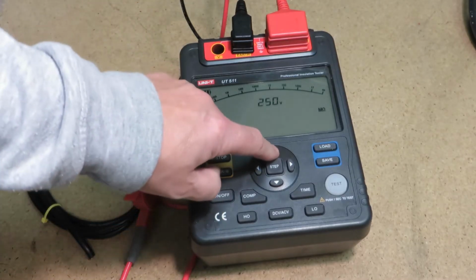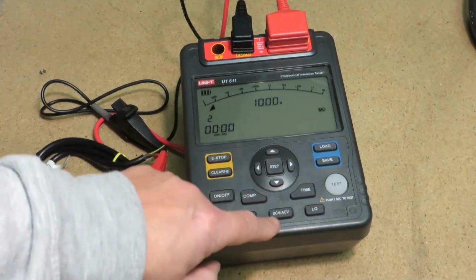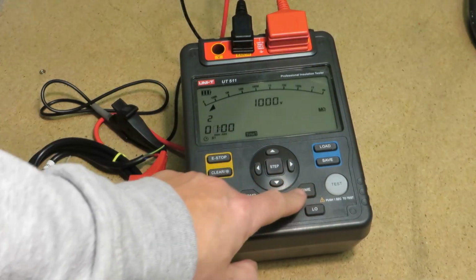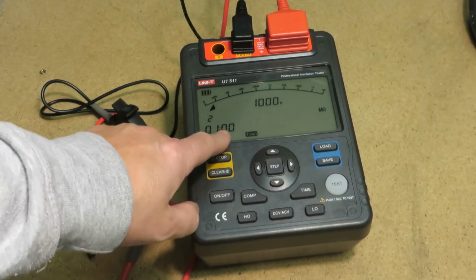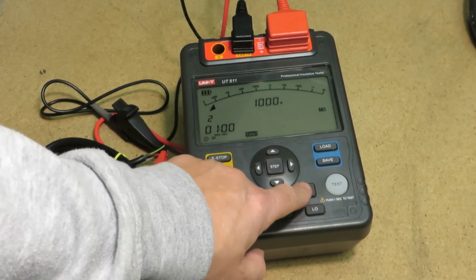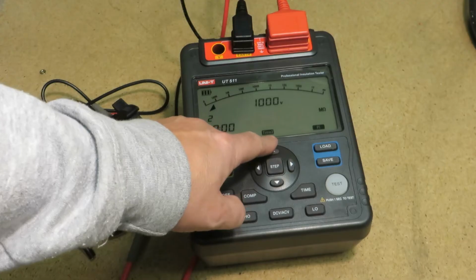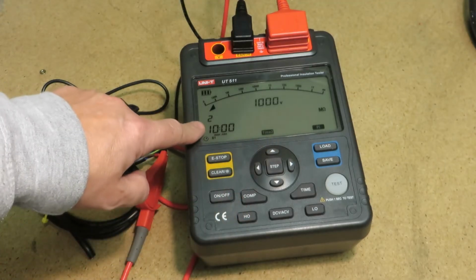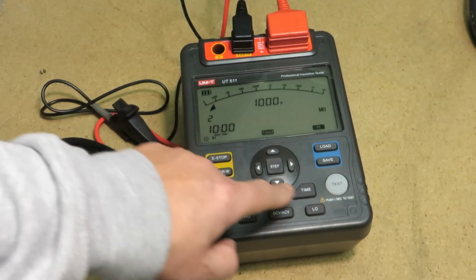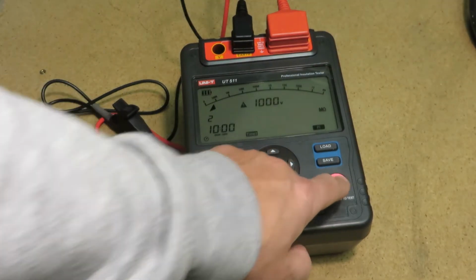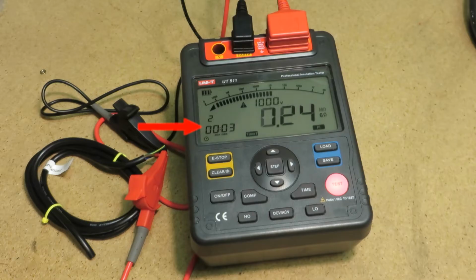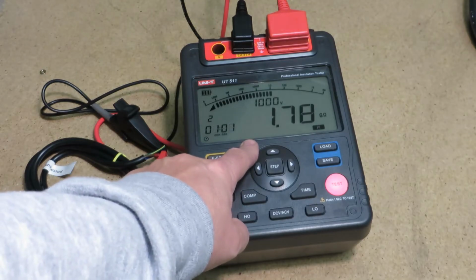For the Pi measurement I choose again 1000 volt and set the first timer by pressing the time button to 1 minute. By pressing time again, you choose the second timer and set it to 10 minutes. That's the standard procedure for a Pi measurement. Press start to execute the operation. The display shows the time for timer 1. After 1 minute, timer 1 has finished and timer 2 starts.